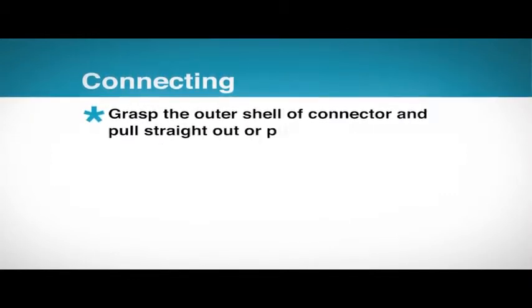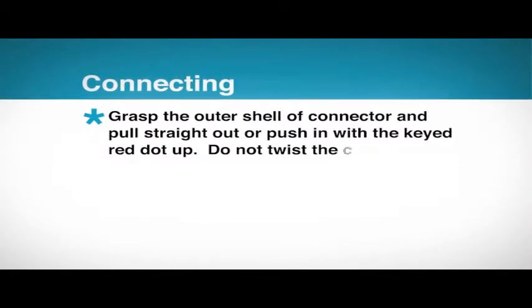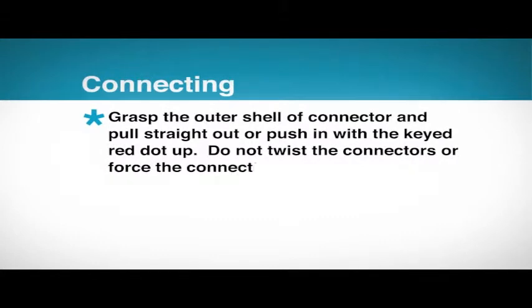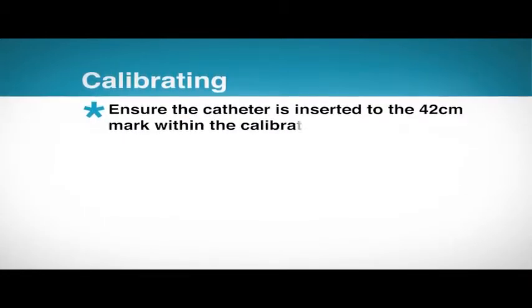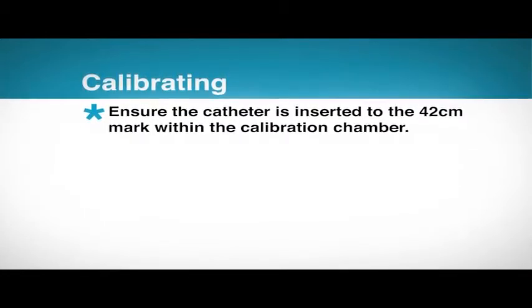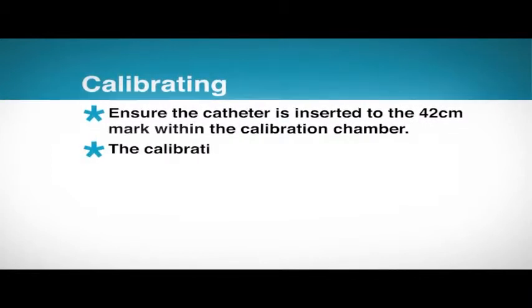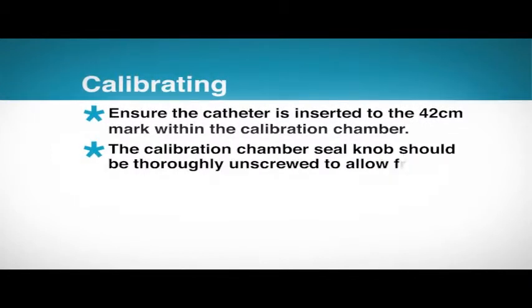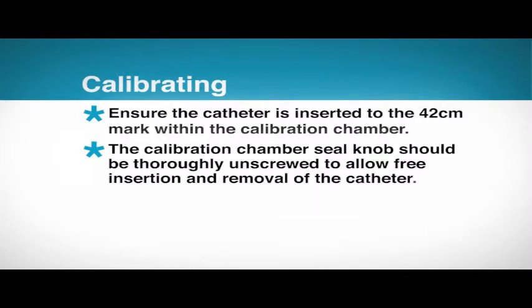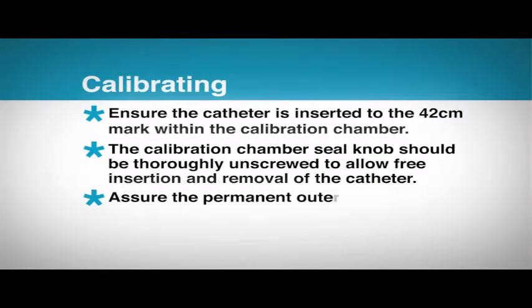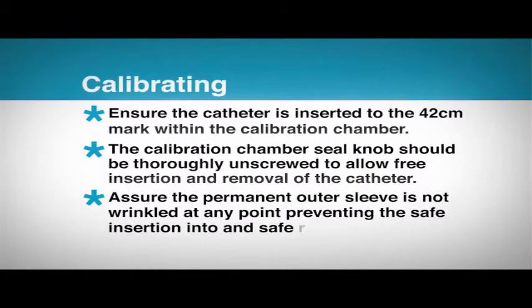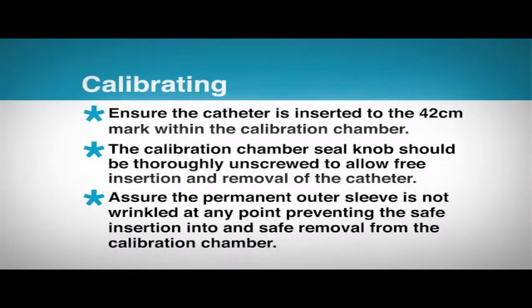Connecting. Grasp the outer shell of connector and pull straight out or push in with the keyed red dot up. Do not twist the connectors or force the connection. Calibrating. Ensure the catheter is inserted to the 42 centimeter mark within the calibration chamber. The calibration chamber seal knob should be thoroughly unscrewed to allow free insertion and removal of the catheter. Assure the permanent outer sleeve is not wrinkled at any point, preventing the safe insertion into and safe removal from the calibration chamber.